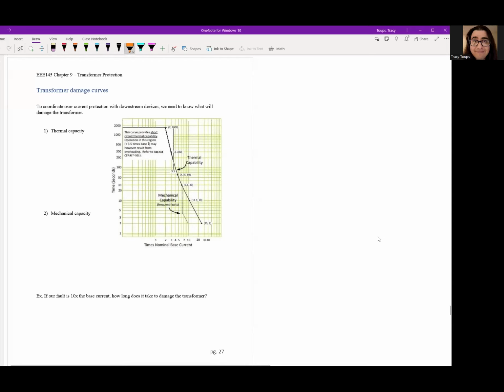So the first thing you always do for a transformer is talk about, well, what's the damage curve? What's the limit the transformer itself can take? So notice the transformer has two curves, right? Every equipment should have this damage curve for you. You have a main curve right here. This is called your thermal curve, and this is the limit of the current before the transformer pretty much burns down. So the limit before a transformer has permanent damage. And you're either fixing it or replacing it at this point. Definitely, you should never ever get to this curve, and if you do, you're probably buying a new one.